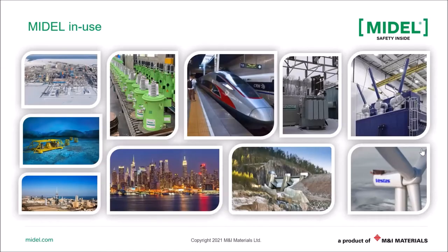Here is a screenshot of the applications in more detail, showing how versatile ester liquids are in use. On the top left corner is a liquid natural gas plant, which is located in the Arctic Circle. In this application, the dielectric liquid has to be able to operate at extreme cold temperatures. And so this is a place where our synthetic ester, MIDEL 7131, is used because it has a pour point of minus 56 degrees C, so it can operate in extreme cold temperatures.